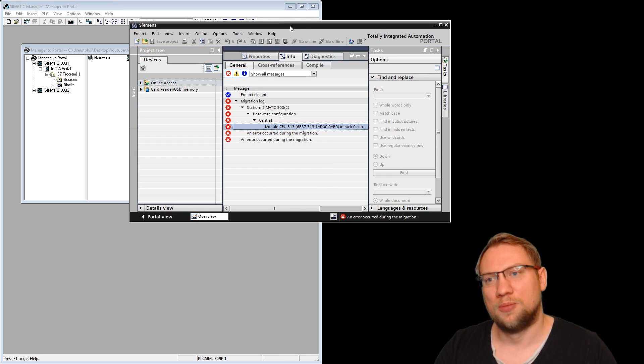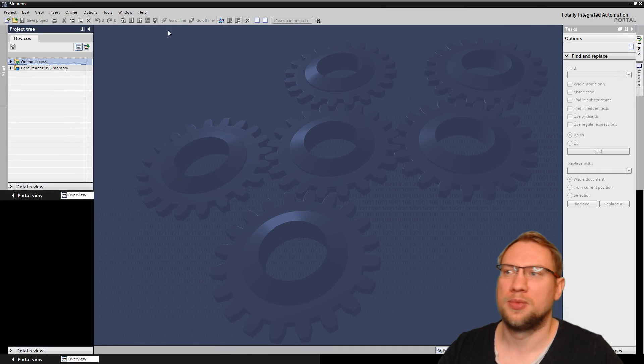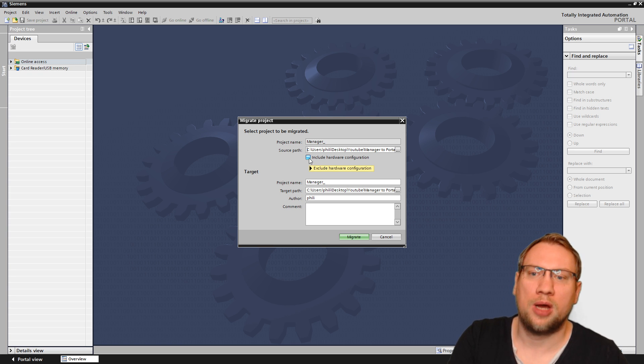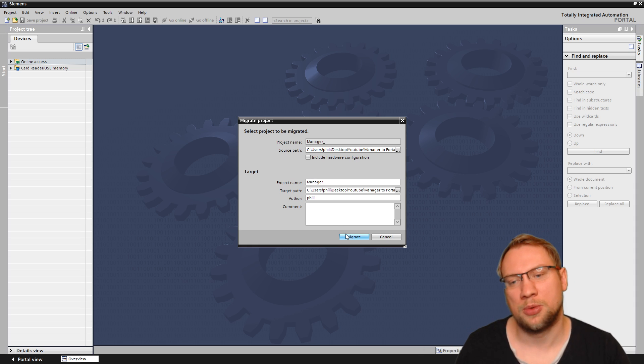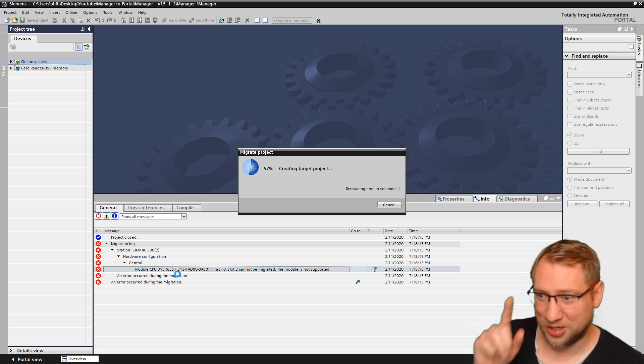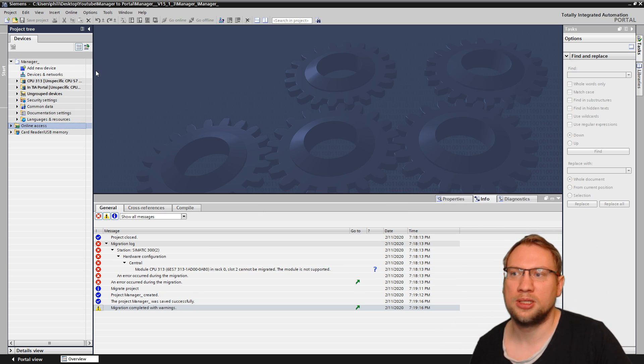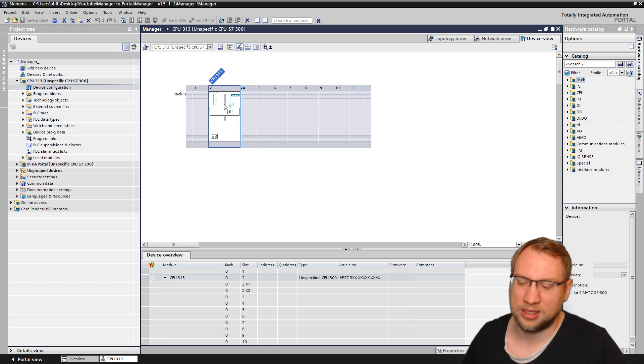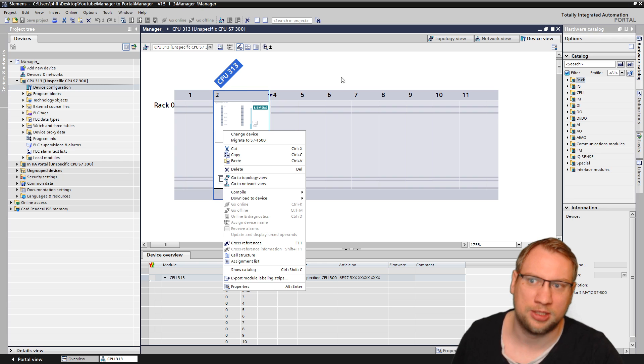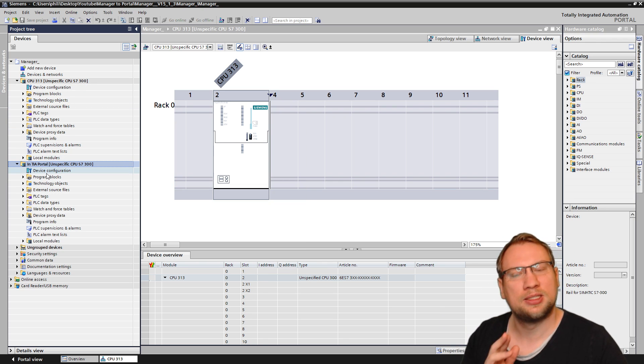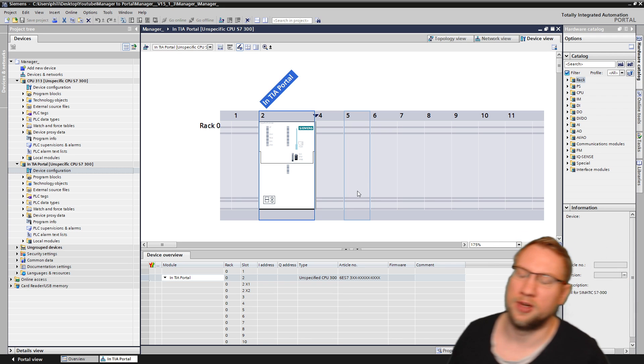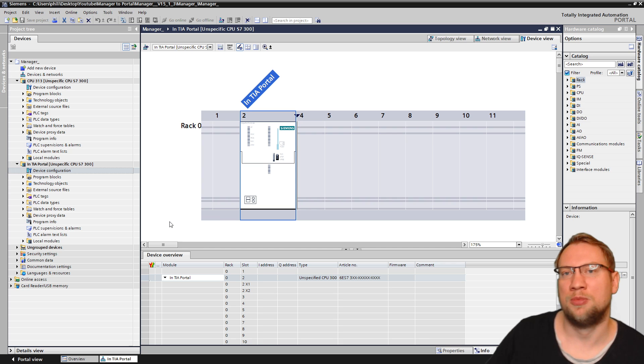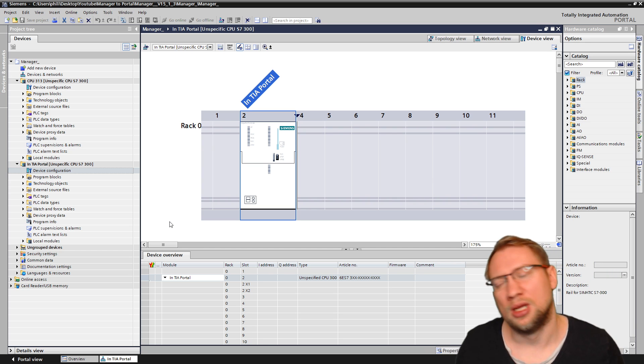This is also the main reason why I still have SIMATIC Manager installed — not all old components are supported by TIA Portal. To actually get this project into TIA Portal, I do the migration again but this time I exclude the hardware configuration. Migration completes with warnings. Now the CPU 313 that was unavailable before shows up as an 'unspecified' CPU — along with the other PLC that also didn't get its hardware imported. We'd have to either migrate it to an S7-1500 or choose a compatible S7-300.